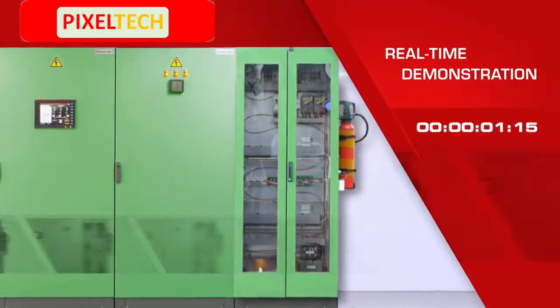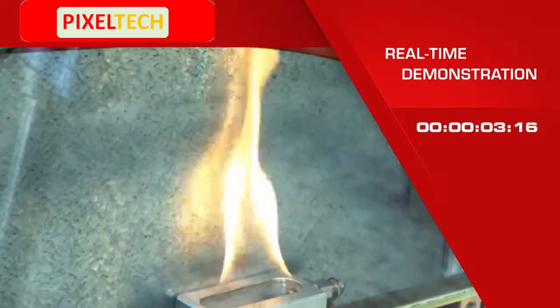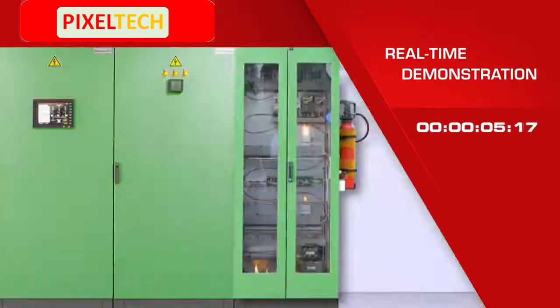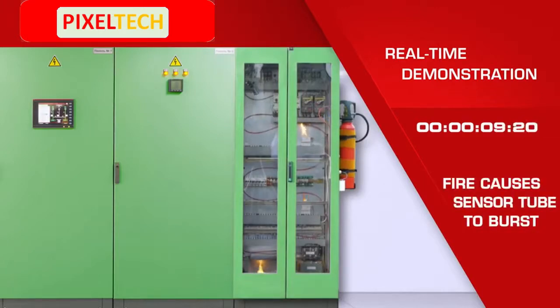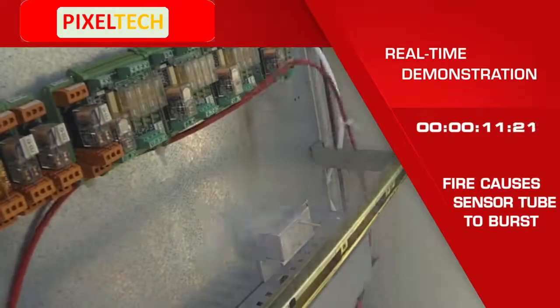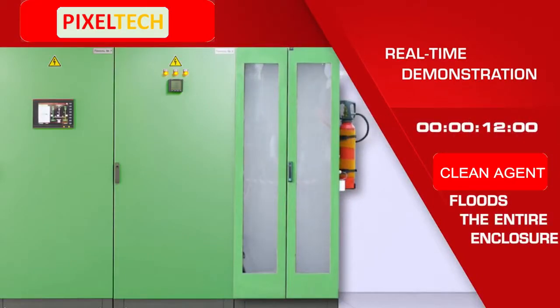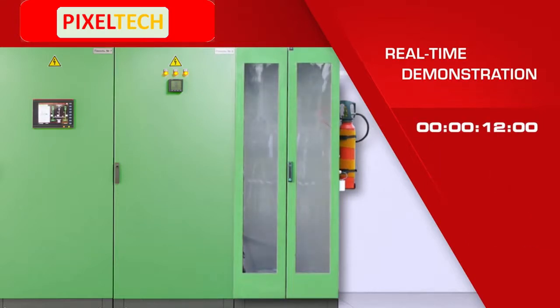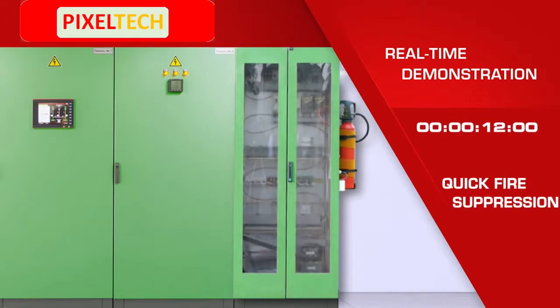Here we demonstrate an electrical fire starting in 3 zones at the same time. Fire causes the pressurized sensor tube to burst at about 110 degrees Celsius. This triggers the immediate discharge of extinguishing agent that rushes out the nozzle at the top of the cabinet and floods the cabinet. The fire is out only 12 seconds after it started.